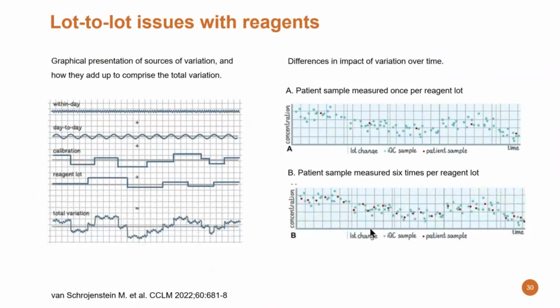I've seen this literature, this publication from van Schrojenstein, which was published last year. And here it's nice to see on the left side how you zoom up with your performance. If you look at the within-day performance, it seems to be quite stable in this situation. So there is only a minor variation between the values. If you look one step down, the day-to-day variation, you see more amplitude behavior of the material. Then if you do calibration, you see that it has a stronger impact on the performance of your instrument and the recovery. And also if you do a lot change without doing calibration, this has an impact. And this ends up in the total variation at the end. If you combine all these variations together, here you see the final total variation on the left side.